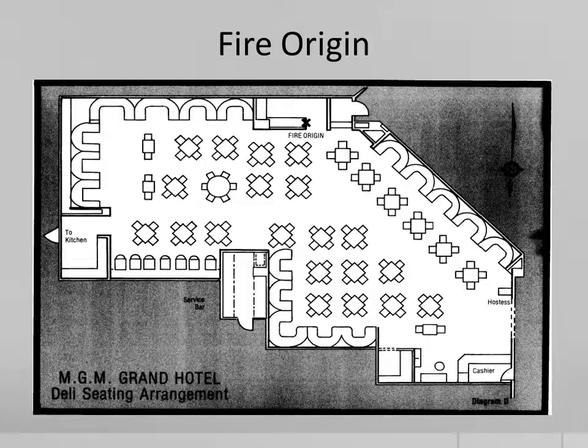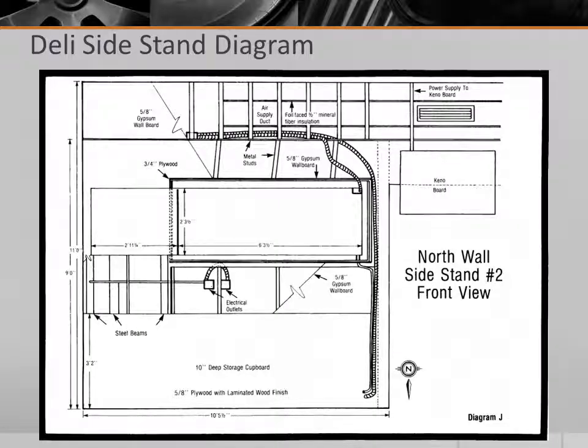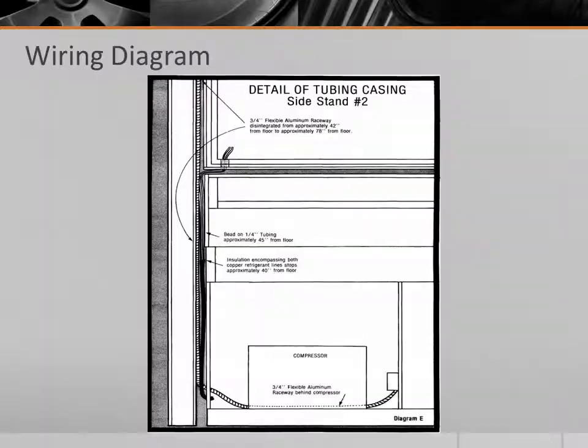This diagram shows the location of the side stand in the deli where the fire originated from. This next diagram illustrates how the side stand area looks from the front, as someone facing it from the outside. This diagram displays the aluminum raceway and wiring that was believed to provide the arc that triggered the fire. The diagram notes damage on the aluminum raceway and insulation.